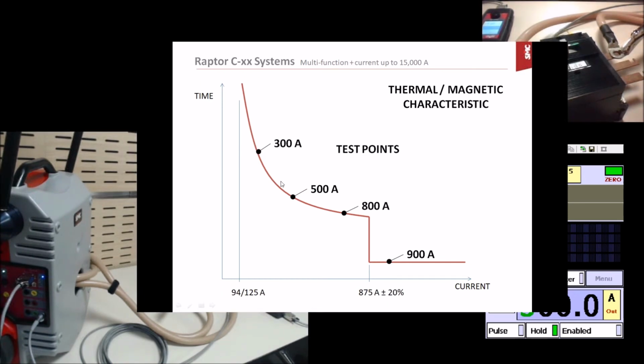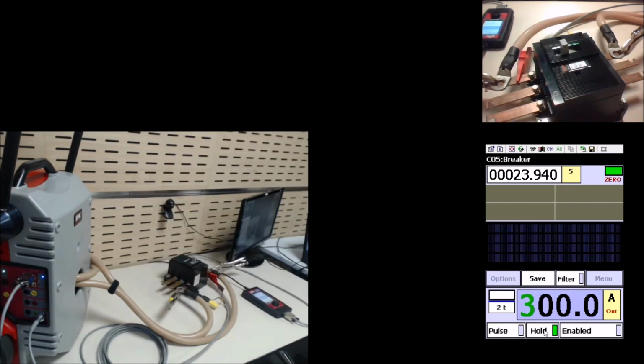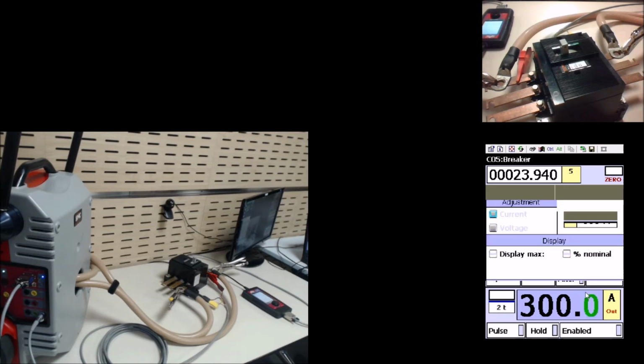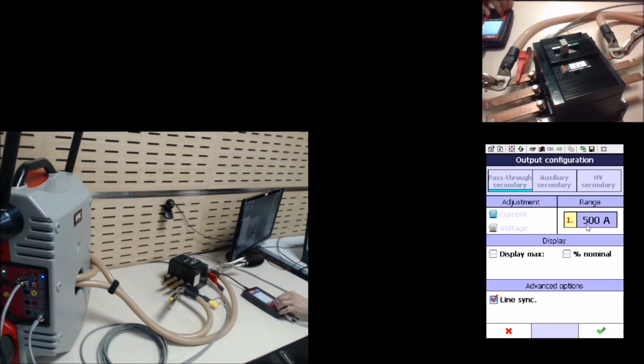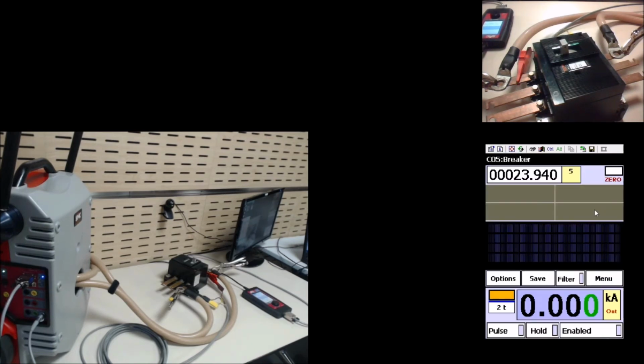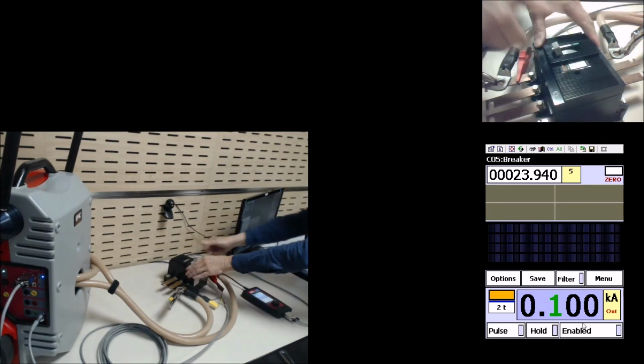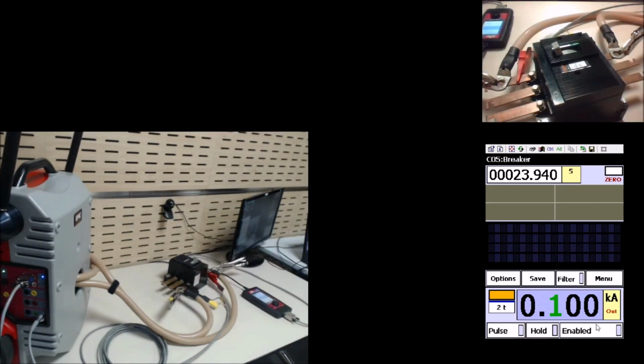All right. So let's go to the second test value, which is 500 ampere. We are going to select now a different adjustment range. Just double click here. We go to a different adjustment range because we have a limit of 500 ampere here. So I'm going to a slightly larger range. For the new range, I need to recalibrate the load. So I enter a small amount of 100 ampere. I reclose the breaker and recalibrate the load for a while. That's it. Now I adjust the actual test value, which is 500 ampere, and press on.